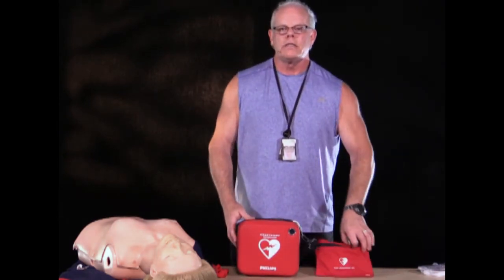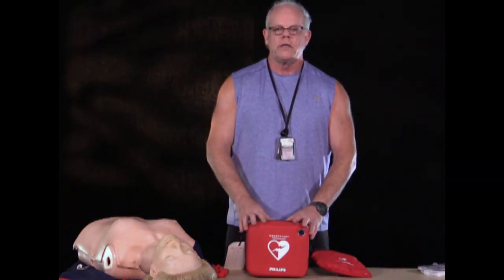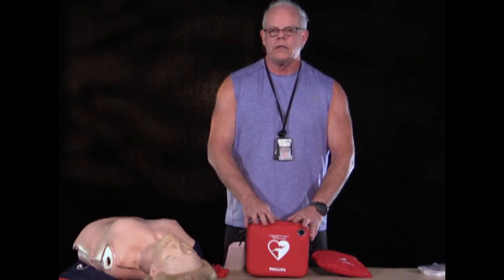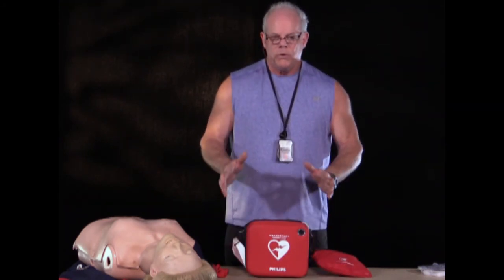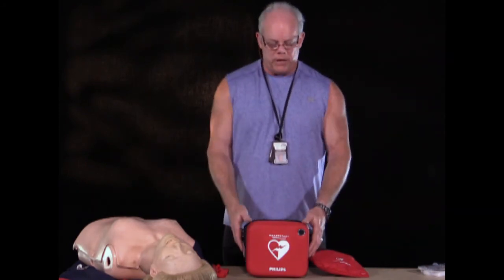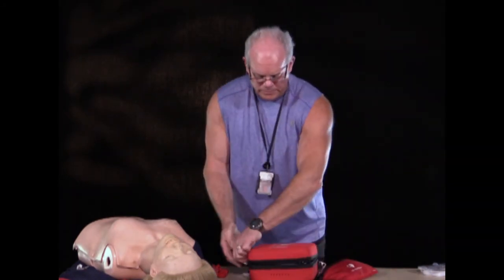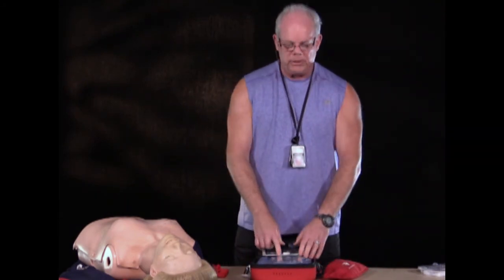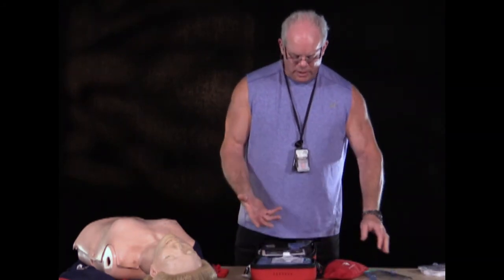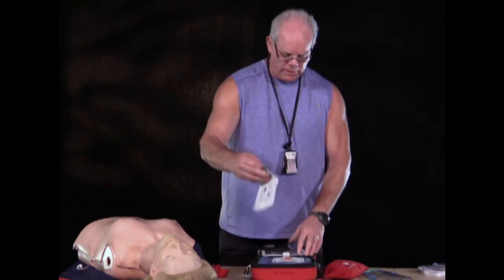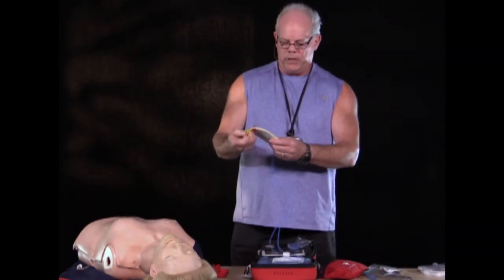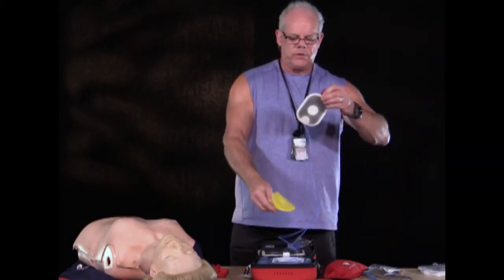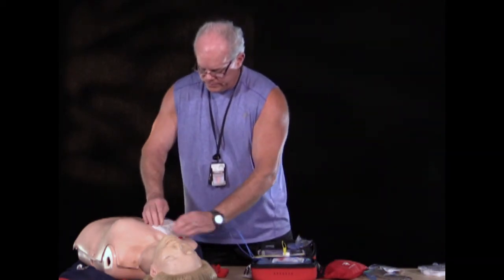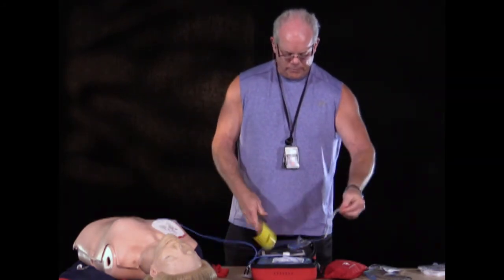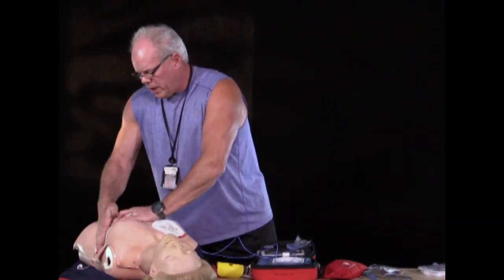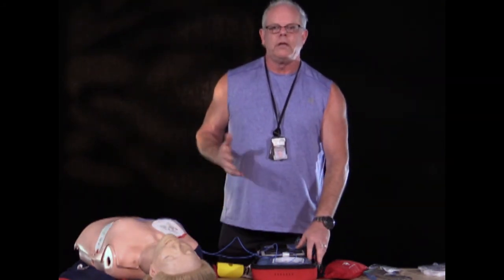Okay, we're back for the last demonstration of the HeartStart. As I said earlier, I replaced the cartridge, so it has a cartridge that is out of date. With this one, if the same situation was happening, a person is down, we get there, we open up the defibrillator, and on the top is a little handle that says pull. I pull that, it pops off. The machine comes on, I pull the tab back, and I've got my pads already here. I look for the pads, the same thing. It's going to go by the clavicle. Adhesive pads. Place pad exactly as shown in the picture. Press firmly.